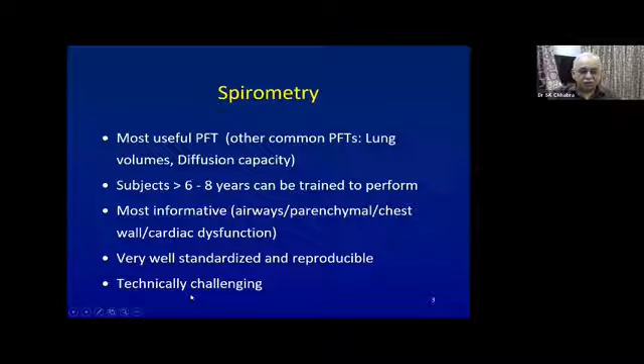You can get totally inaccurate results if spirometry is not done properly. It's not a question of just blowing into the machine, but it's a question of doing it properly. And there are several aspects to the quality control which the technician as well as the person in charge of the lab must exercise. First begins with the purchase of the equipment. There are different kinds of spirometers available in the market. The one that you should go in for should be meeting the specifications of the American Thoracic Society and European Respiratory Society. Now, these technical specifications are laid out, and your equipment must perform according to these specifications. And usually the manufacturer will give a certificate that this is as per the specifications.